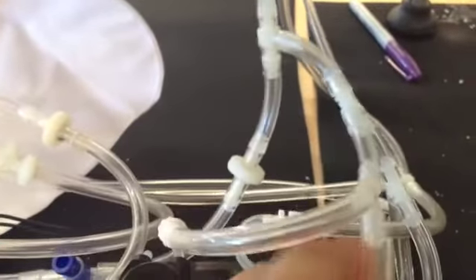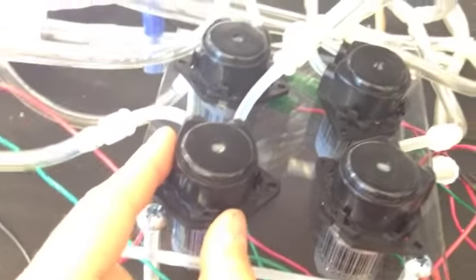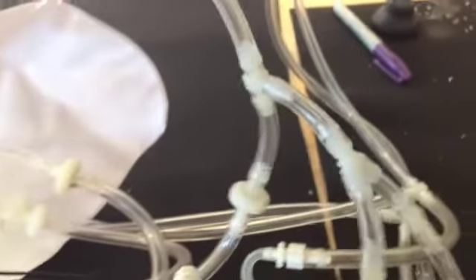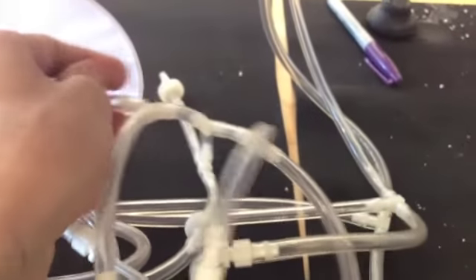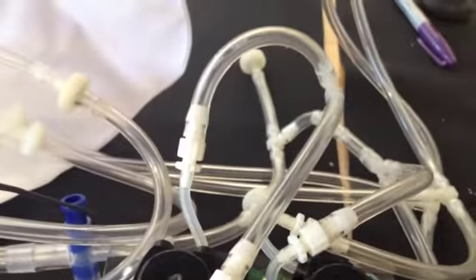After the pump, the two sides connect together again. The nice thing about the pumps is they don't let any transfer from one side to the other without running, so being connected together isn't a bad thing at all. There's a bunch of check valves which get kind of complicated to explain, but they're basically put in the right places to work.